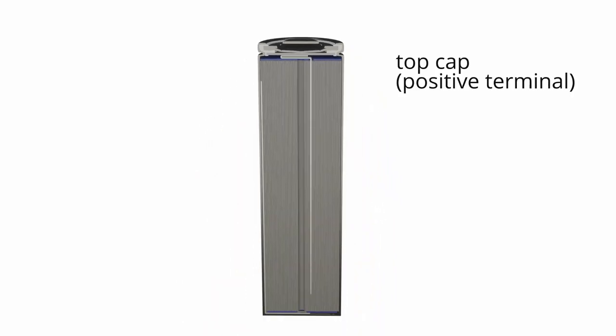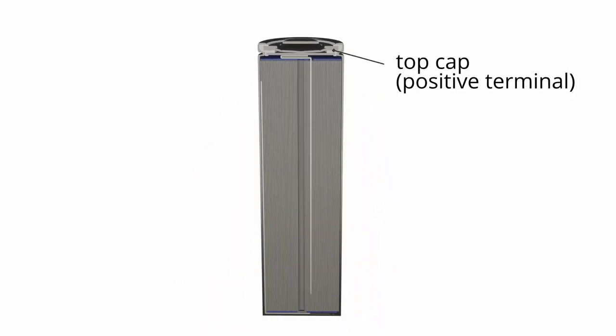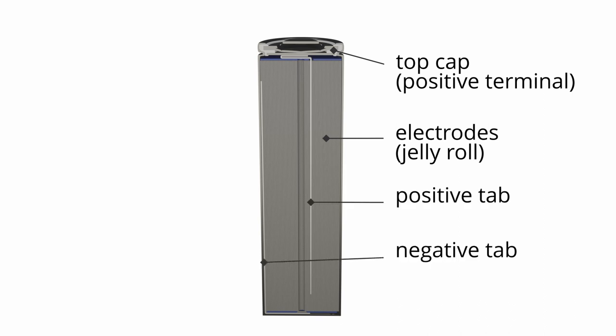To understand better how the CID works, we have to take a closer look at the internal construction of a cylindrical lithium-ion cell. The CID is located in the top cap of the cell. The electrodes, which are wound to a cylindrical shape, are connected to the cell can and to the positive terminal through one or more tabs. The CID is located between the electrodes and the positive terminal, and can therefore cut this connection.